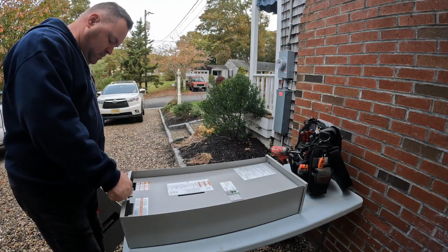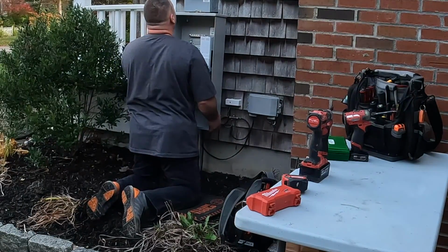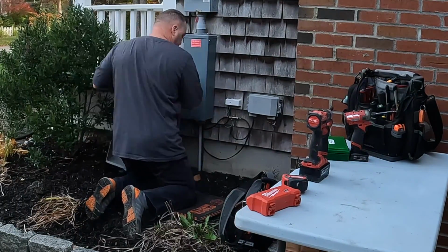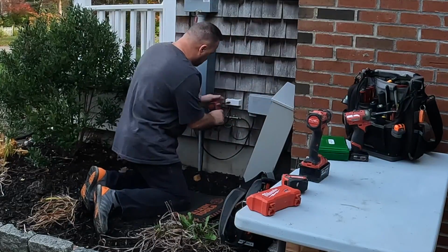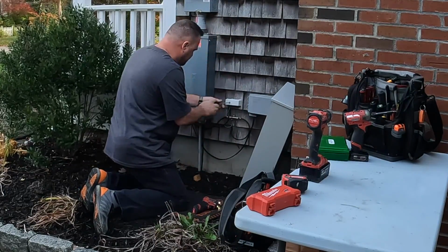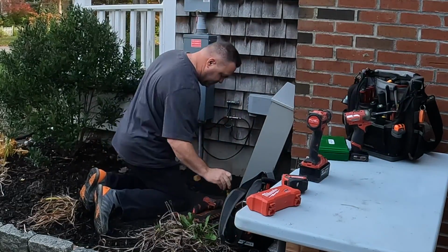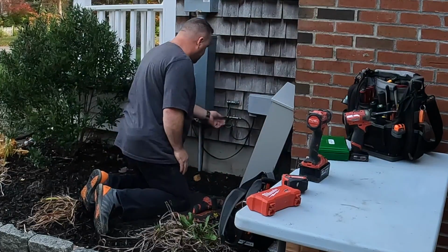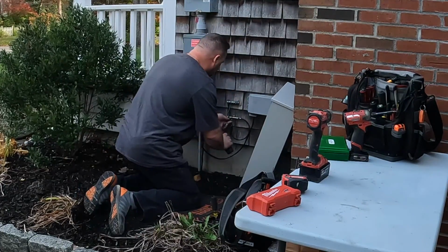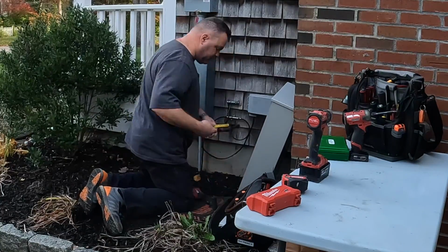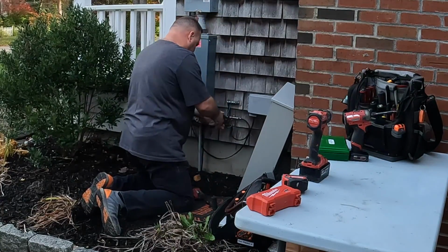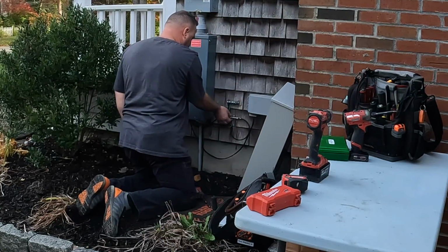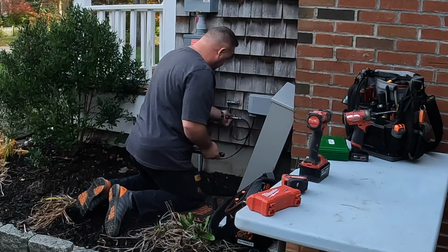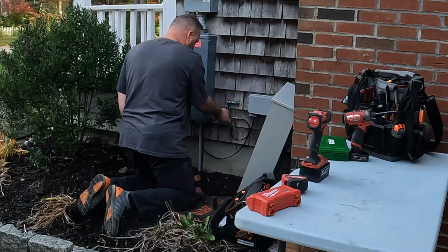Obviously, we need to do the main utility supply. That would be L1 and L2. And then we also have to install the wiring from the generator to the emergency connections inside this generator, which we'll go over later. And then, of course, we need to have the wiring that goes to the electrical panel. So there's 3 sources of conductors: the line side, the generator side, and then the customer load.